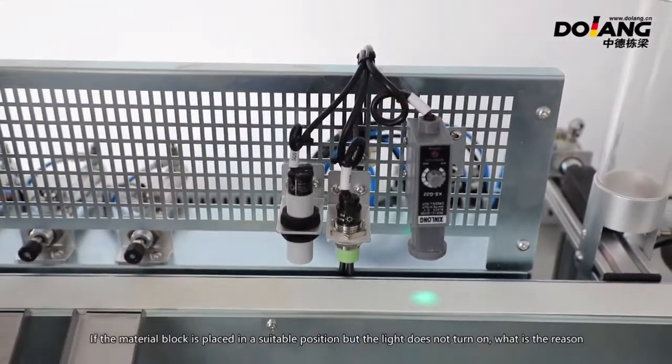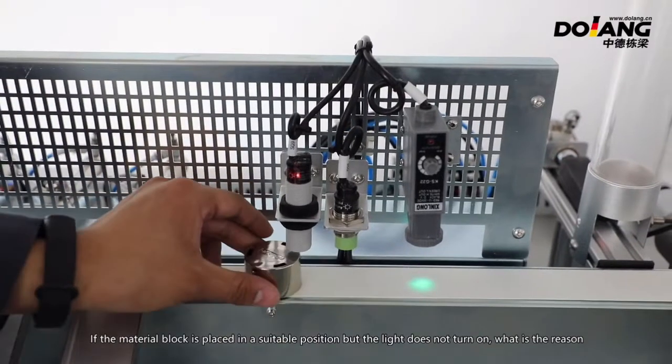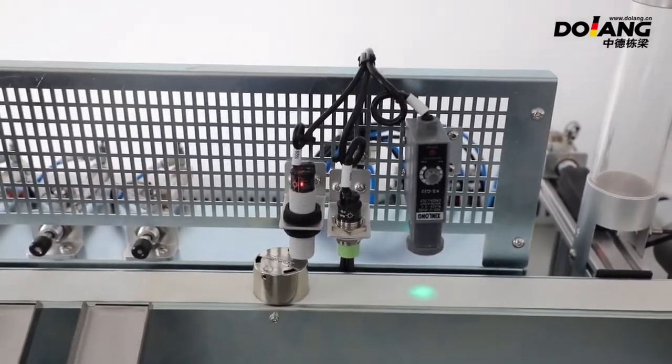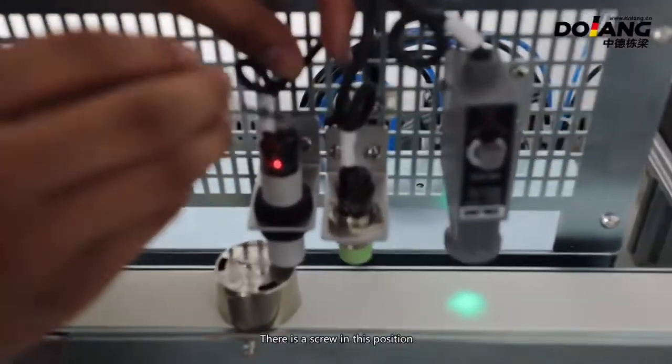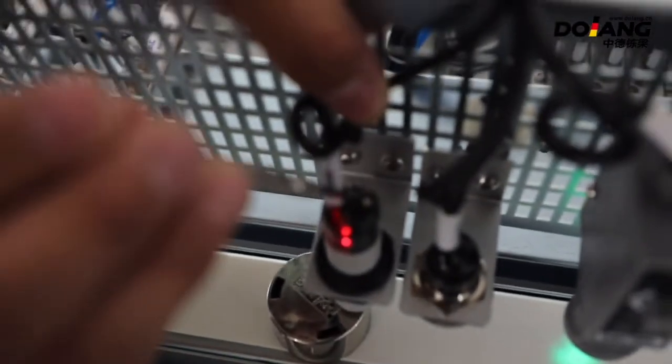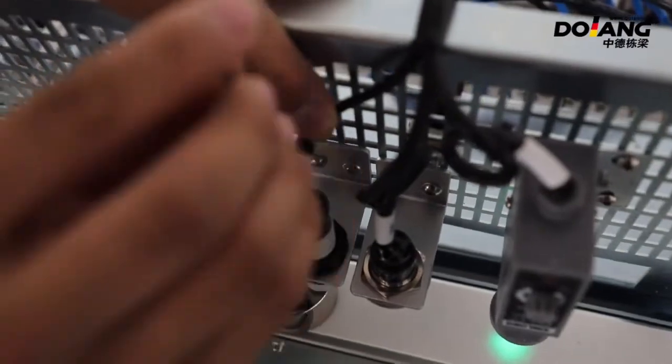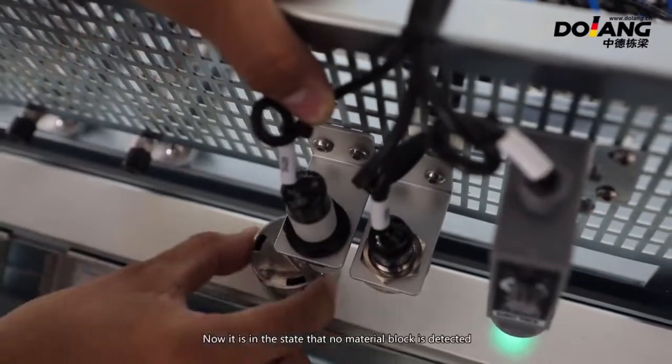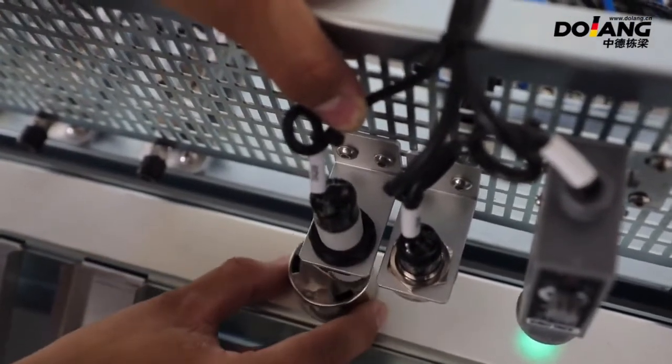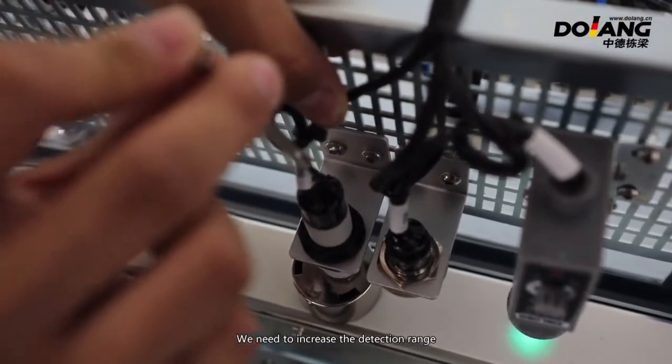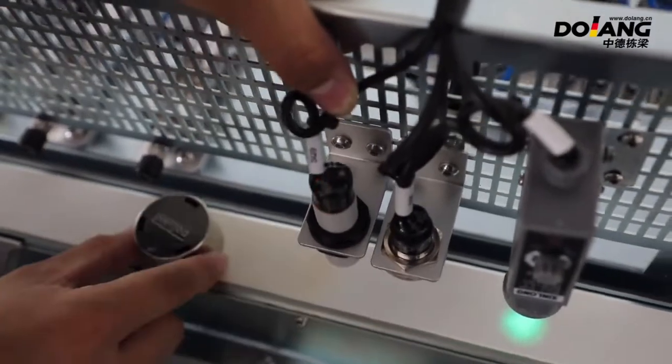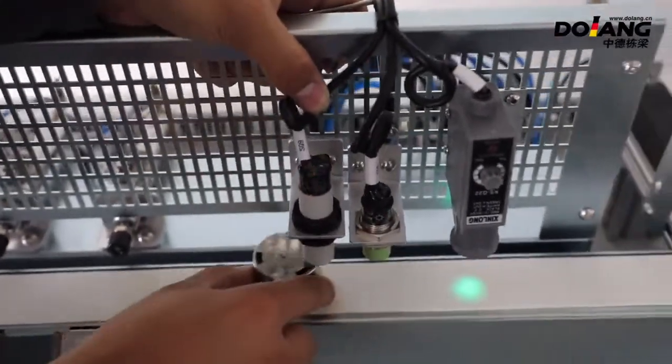If the material block is placed in a suitable position but the light does not turn on, what is the reason? There is a screw in this position. This determines the sensor detection distance. Twist it a little. Now it's in the state that no material block is detected. We need to increase the detection range. It's okay now.